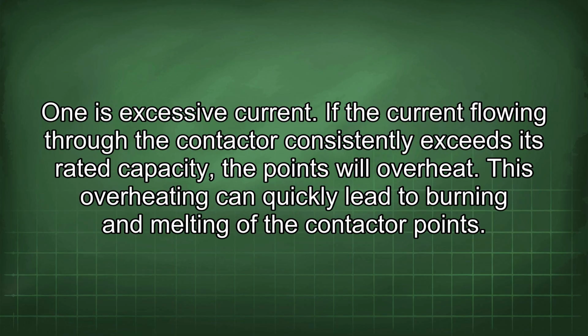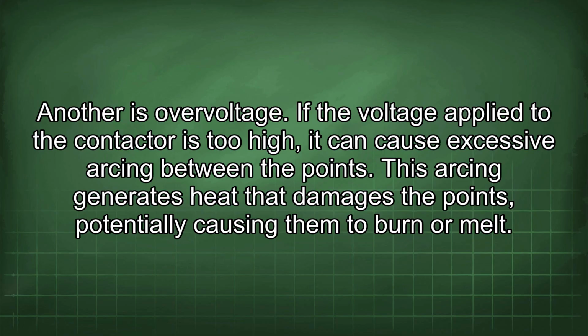One is excessive current. If the current flowing through the contactor consistently exceeds its rated capacity, the points will overheat. This overheating can quickly lead to burning and melting of the contactor points. Another is overvoltage. If the voltage applied to the contactor is too high, it can cause excessive arcing between the points. This arcing generates heat that damages the points, potentially causing them to burn or melt.